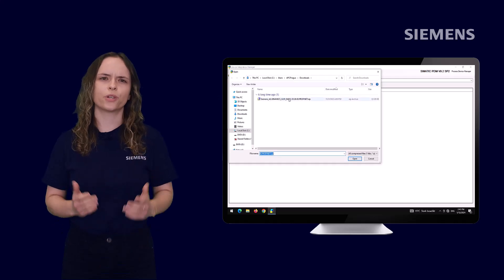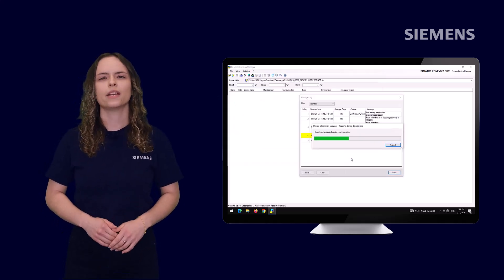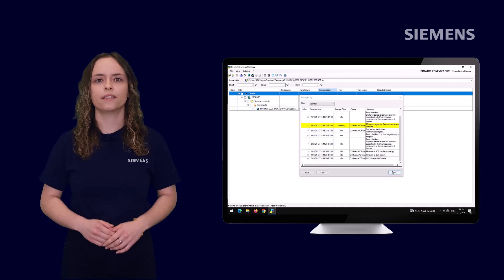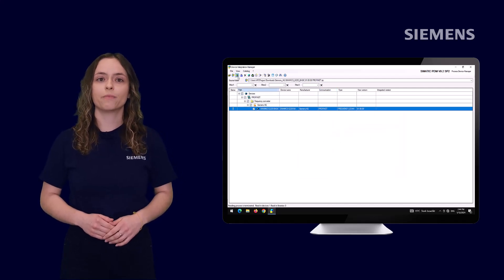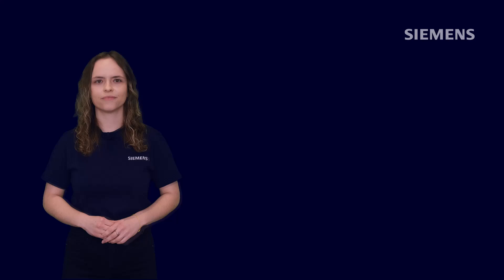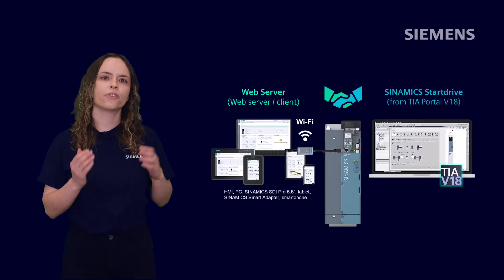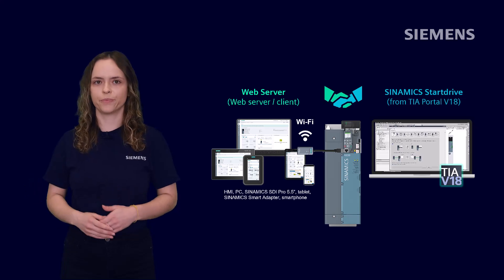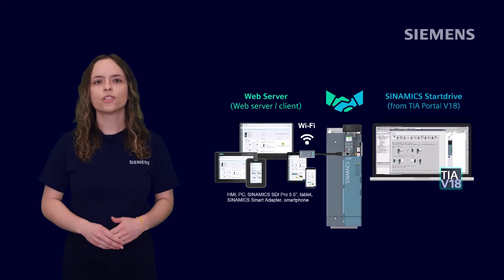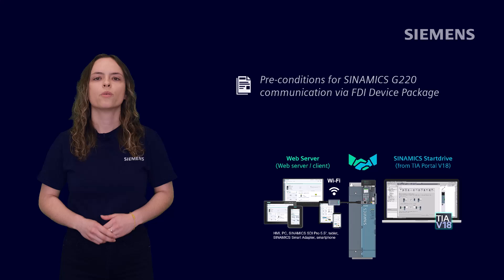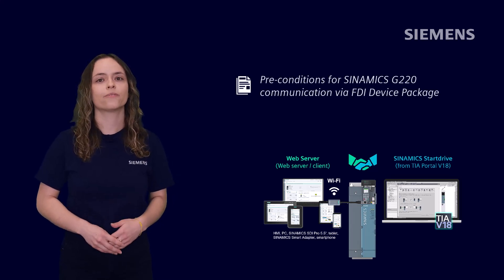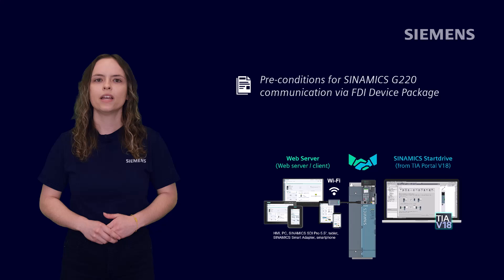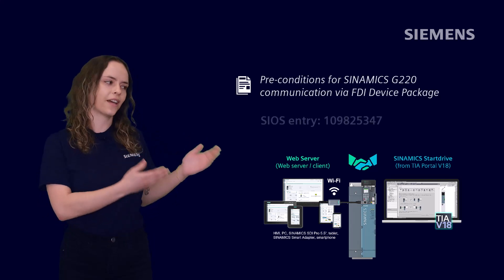For integration of the Sinamics G220 into PDM, it is necessary to get the FDI device package, which is provided by Siemens for free. The initial commissioning of the Sinamics G220 drive is done via standard commissioning tools, either via the integrated web server or Startdrive in the TIA portal. For the initial setup, please use the guide 'Pre-conditions for Sinamics G220 communication via FDI device package,' which can be found on this SIOS entry.